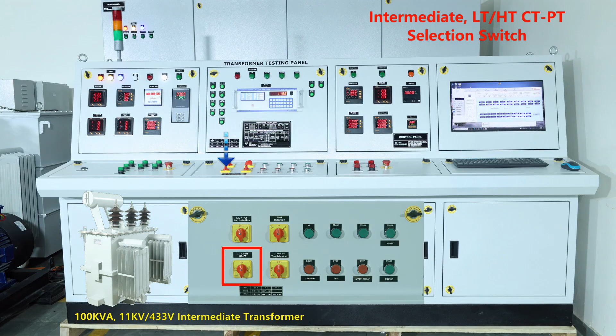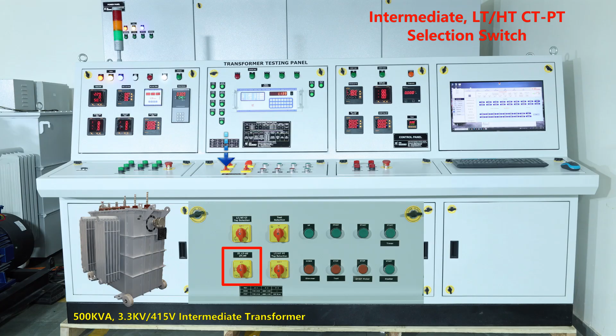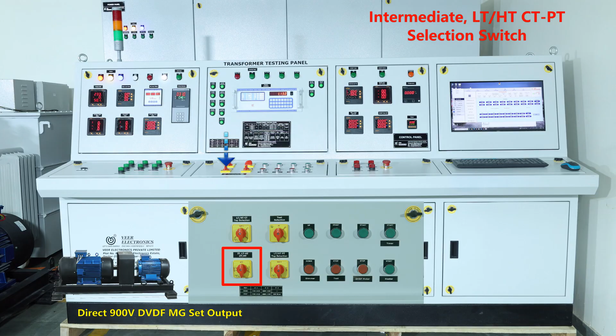Second is 500 kVA, 3.3 kV by 415 volts intermediate transformer to perform short circuit and temperature rise test of transformer. Third intermediate selection is 900 volts direct output for DVDF test of distribution transformer. HT and LT, CT and PT are also selected by this switch.